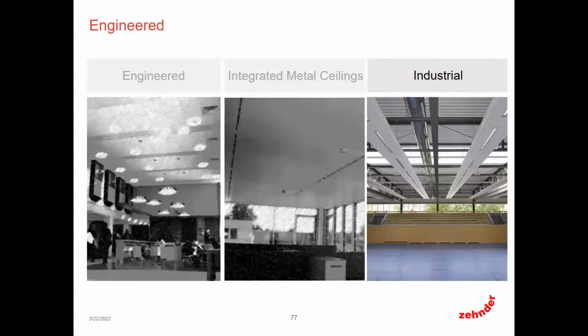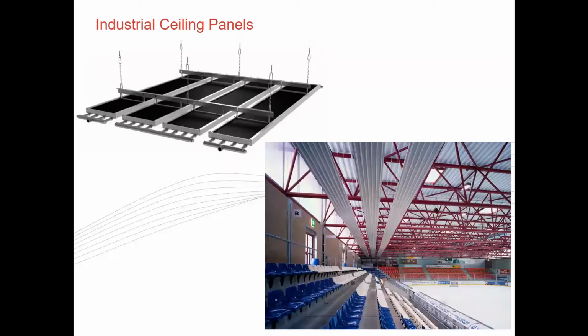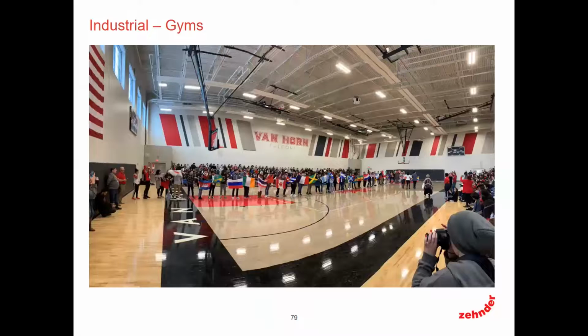All right, so the last market here, and I'm going to get through this real quick because we've got a couple minutes, is more of the industrial look. These panels are meant to be a low-cost installation. Typically, they come in longer runs. You'll see these up to 20-foot strips, and they can go in combinations from a single panel strip all the way up into a 4-panel configuration. These go into typically larger bay production facilities, gyms, non-cooling applications, although the panels themselves can be used for cooling. But applications like these are traditionally heating only.